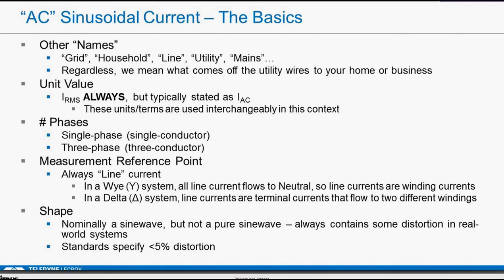And as we described before, in a Y system, all line current flows to neutral. So line currents are what would be called a winding current. In a delta system, the line currents are terminal currents that flow to two different windings. So just something to be aware of there. And the shape, it's nominally a sine wave as delivered by the utility, but not a pure sine wave. There's always some distortion. The standards usually specify no more than 5%.